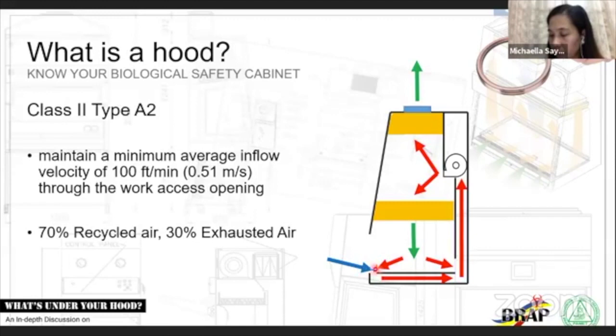It sucks in, again, both grills, front and rear, up to a plenum, goes to your biosafety blower. It gets pushed here. Portion of that goes out. Portion of that goes back in to your work area. So similar principle with your A1. Clean air produces a clean environment here. Ensures that if you manipulate aerosols in this portion, no particles go here, or most importantly, go here.